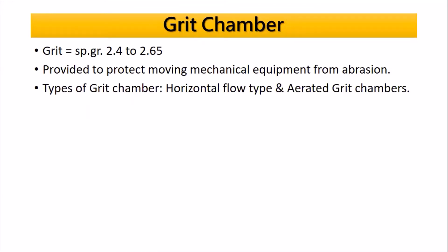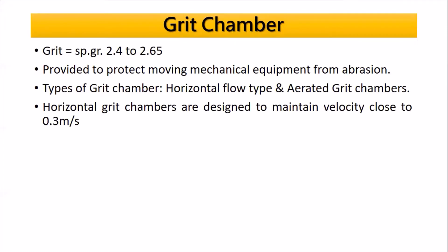The main object of the grit chamber is to remove grit and sand at the bottom of the tank. The specified detention time provided in the grit chamber is one minute, equal to 60 seconds. The specific gravity of grit is 2.4 to 2.65. It provides protection for moving mechanical equipment from abrasion. Types of grit chamber include horizontal flow type and aerated grit chamber.